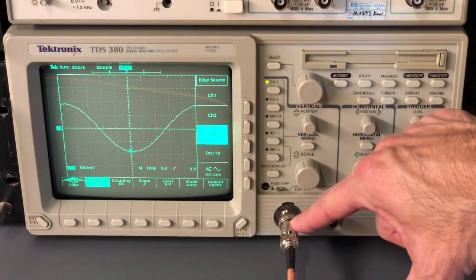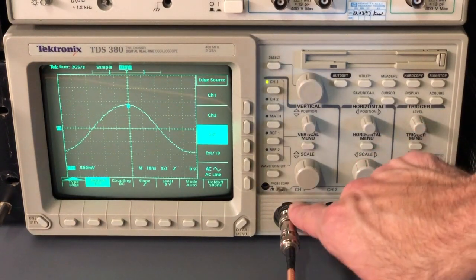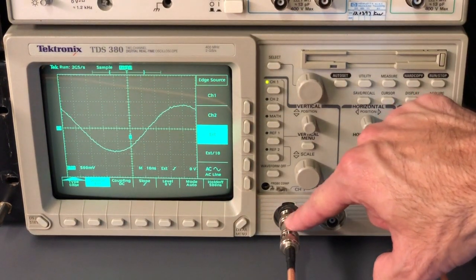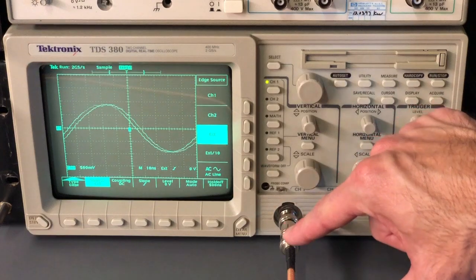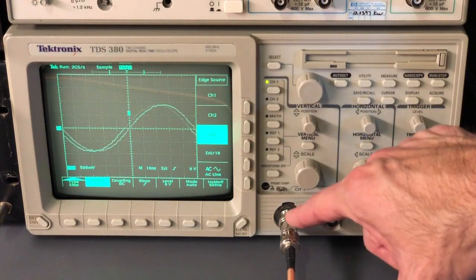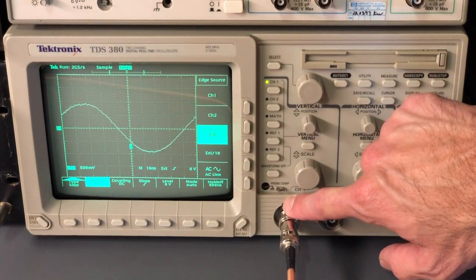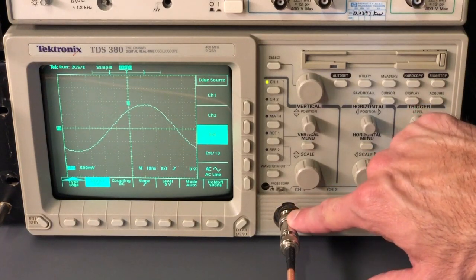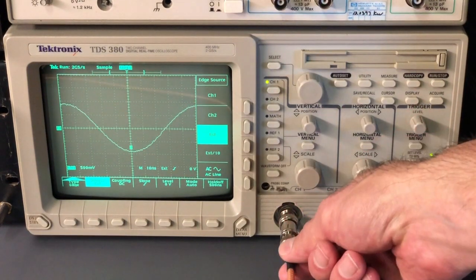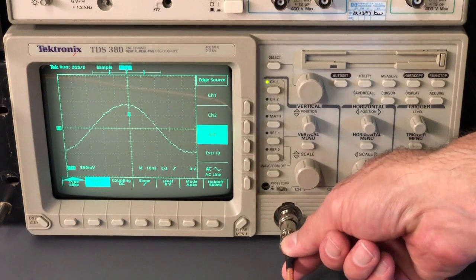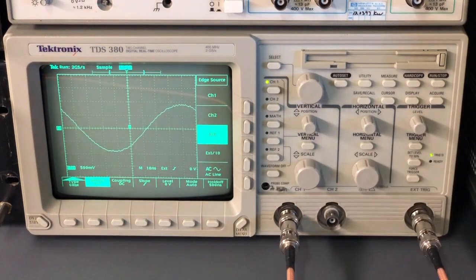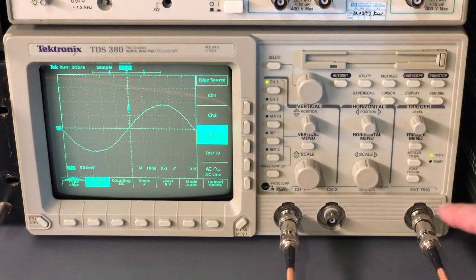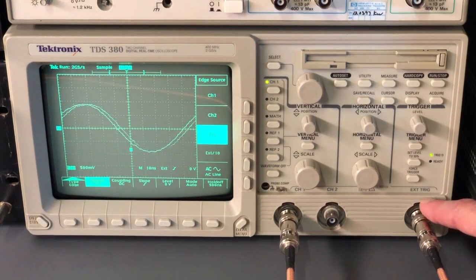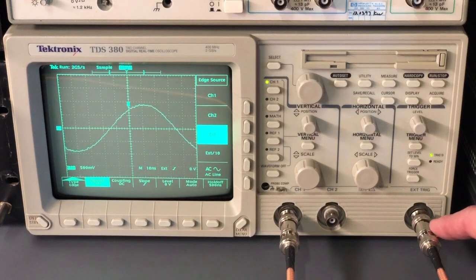This is a 50 ohm feed-through termination, so the signal goes through this termination. This applies 50 ohms from the center conductor to the outside shield of the coax. This is a very high input impedance on the oscilloscope, so you want to terminate that into 50 ohms because it eliminates any reflections that may occur on this coax. The frequency counter expects to see a 50 ohm impedance.